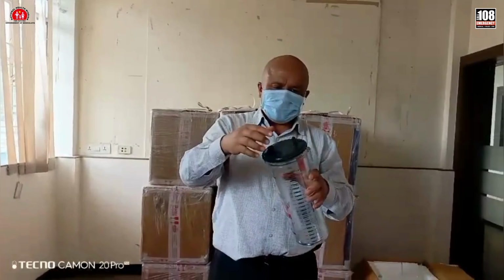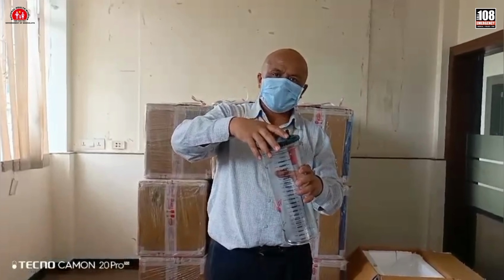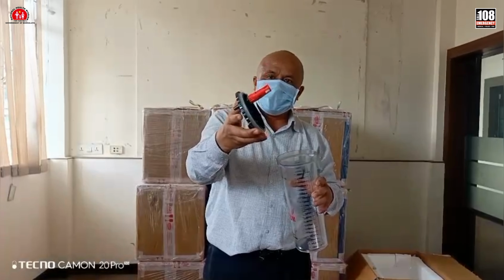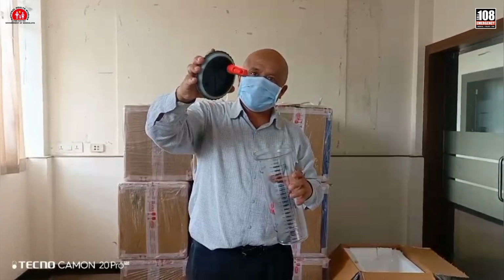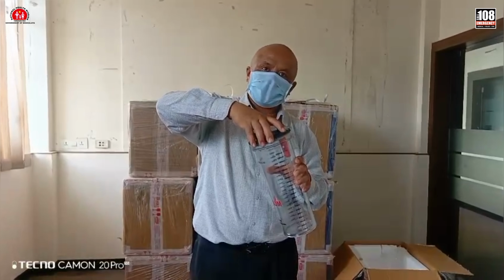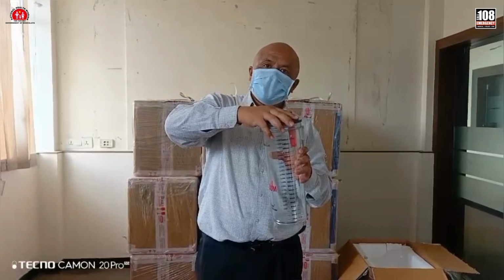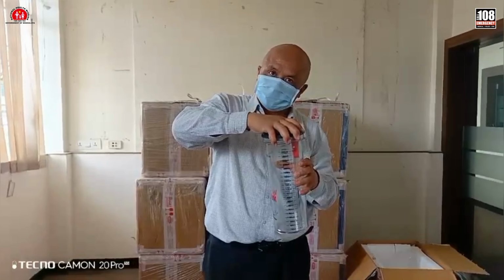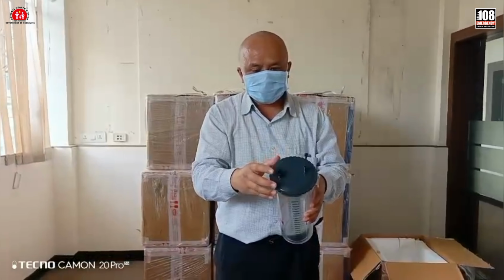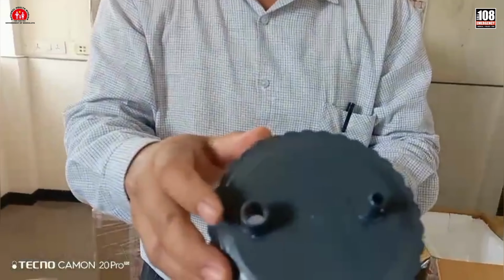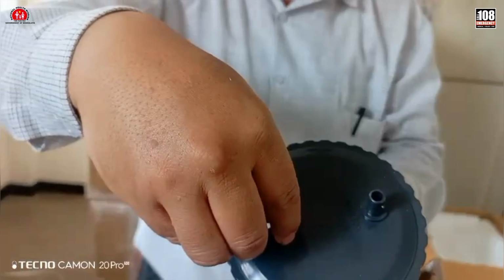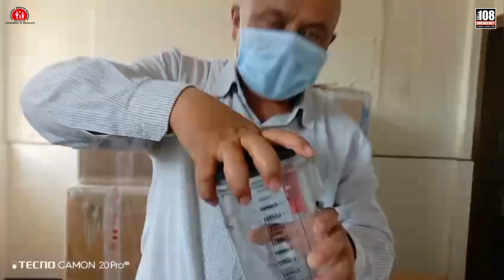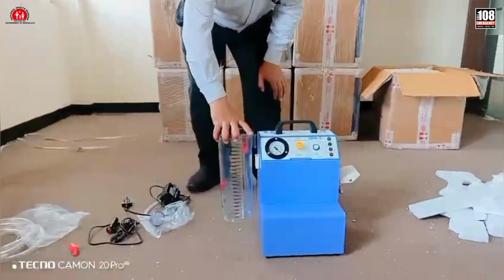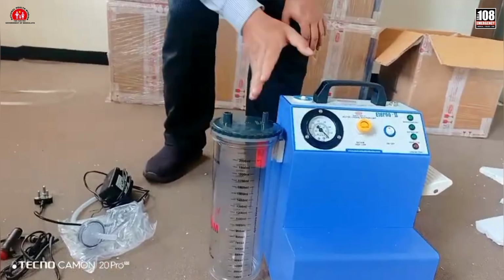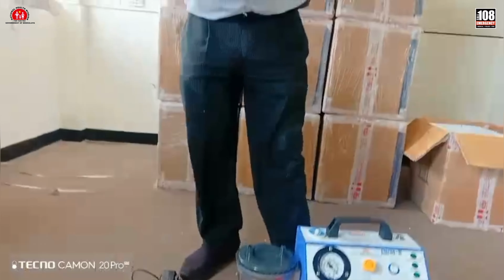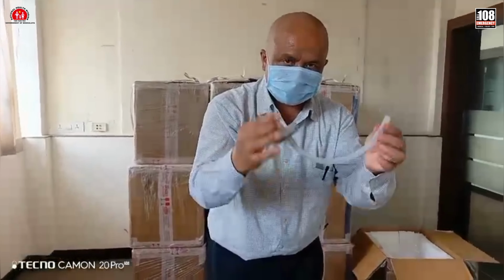Now, you can see this collection jar has got a cap or a lid. Inside this lid, there is a filter which will protect the vacuum chamber of the suction machine from getting contaminated with the suction fluid. Now, in the cap, there are 2 connectors again. On one, you'll put a red connector, and on the other you'll put a machine tube. So how do we use that? Just have a look. You hang this collection bottle at the side of the machine, and then you take a machine tube. This is called a machine tube.